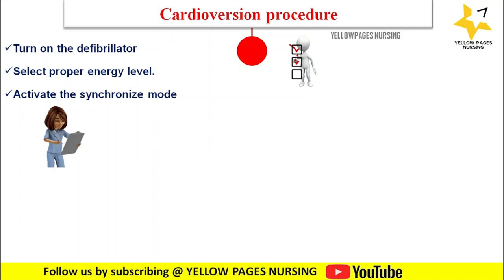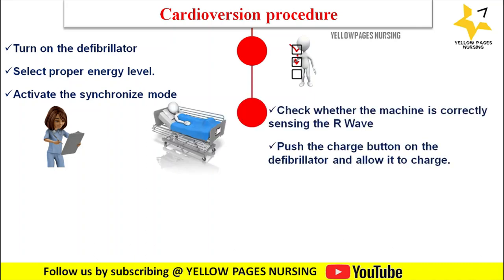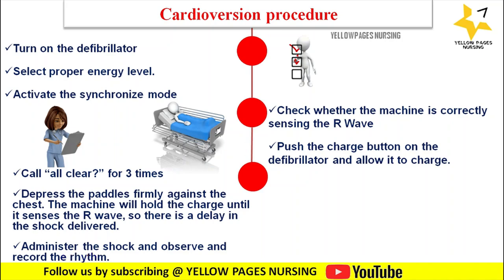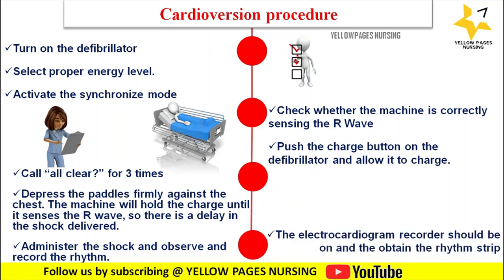Turn on the defibrillator and select the proper energy level. Activate the synchronized mode and check that the machine is correctly sensing the R wave. Push the charge button and allow it to charge. Call clear three times before pressing the discharge button: on the first call, ensure you are not touching the patient, bed, or equipment; on the second call, ensure no one is touching the bed, patient, or equipment; on the third call, perform a final visual check that you and everyone else are clear. Depress the paddles firmly against the chest — the machine will hold the charge until it senses the R wave, causing a delay. Administer the shock, then observe and record the rhythm. If the arrhythmia is not corrected, repeat the procedure using the next energy level.